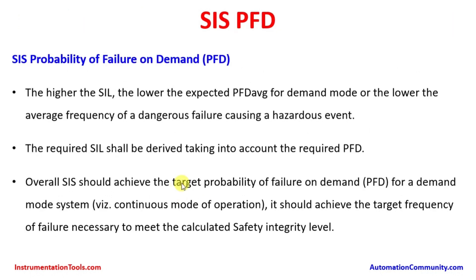For Probability of Failure on Demand, the higher the Safety Integrity Level SIL, the lower the expected PFD average for demand mode, or the lower the average frequency of a dangerous failure causing a hazardous event. A hazardous event happens in plants whenever there is any dangerous failure in a particular component such as a sensor or Final Control Element. When the SIL is higher, the PFD average is lower. The required SIL shall be derived taking into account the required PFD.